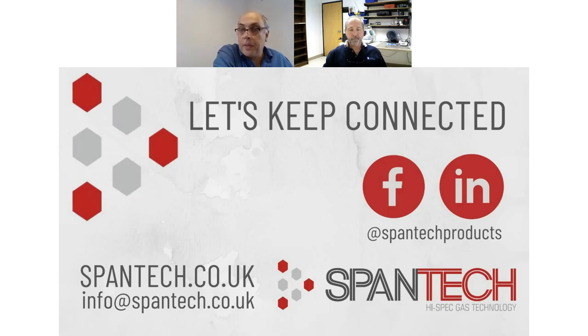Good. So I think the last question we have is regarding chlorine dioxide generators. In the chlorine dioxide generators, the electrolyte needs to be changed every 2 months. Can you please tell us why? The observation is that in a chlorine generator, the electrolyte can last for years. How does ACD manage the problem to ensure that the generator will last for at least its 12 months, 1 year NIST certification?